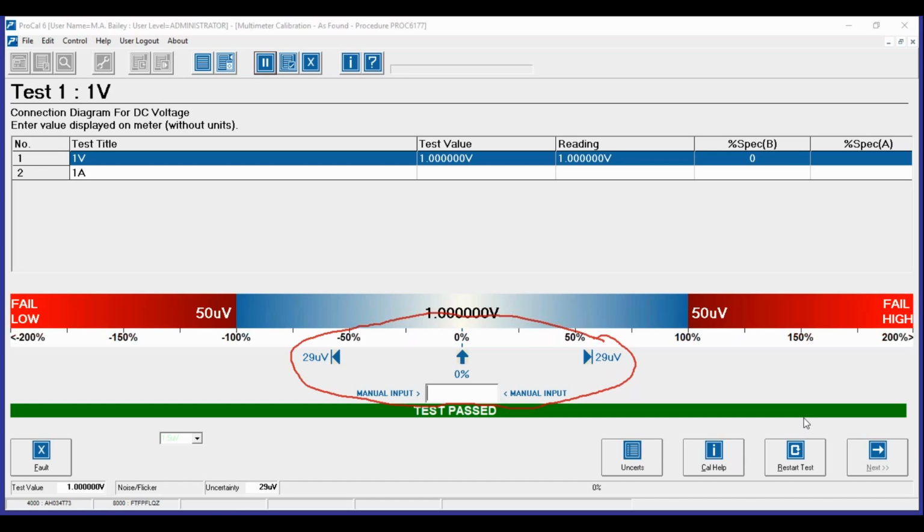The way we perform this is to develop our schedule. We have a special procedure we run that lists our best measurement capability, and then we can compare that every couple of months to make sure our uncertainty tables, or our imported ones, haven't had an effect on our schedule, making sure that it's never smaller than our published schedule.